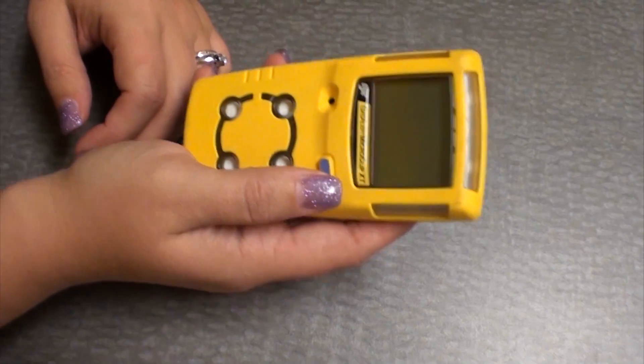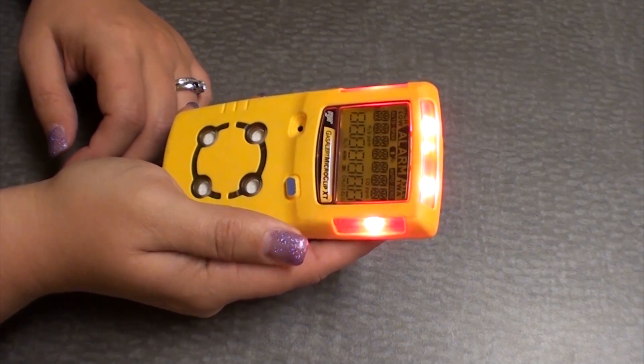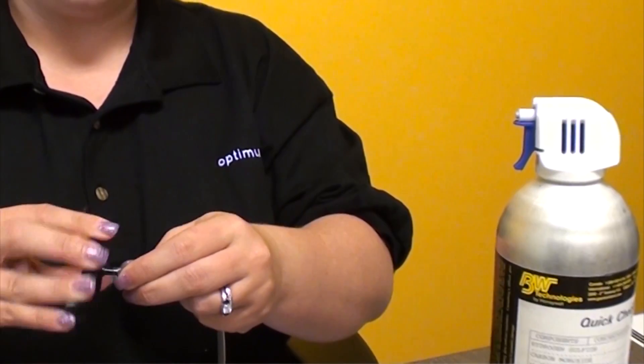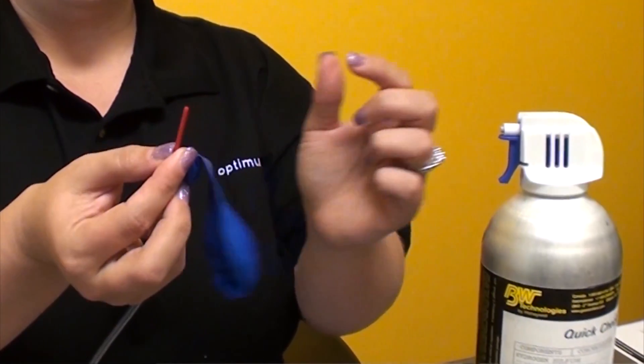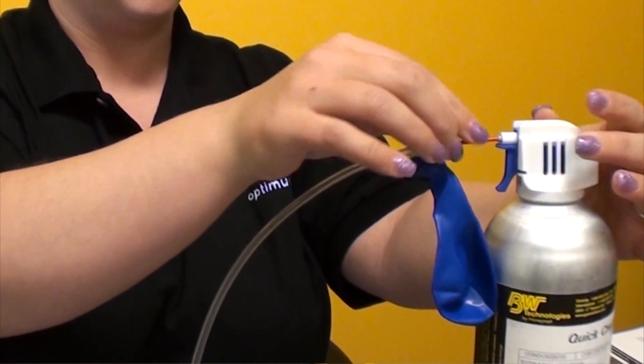Today we're going to do a bump test of a GasAlert MicroClip XD. The first step is to turn your MicroClip on. While you're waiting for the unit to turn on, you can make sure that your test cap and hoses are all attached together and connected as they should be to your bump gas cylinder.